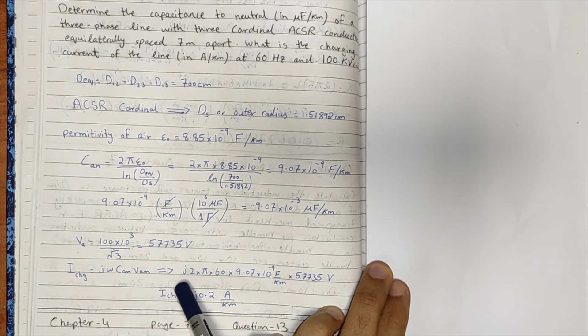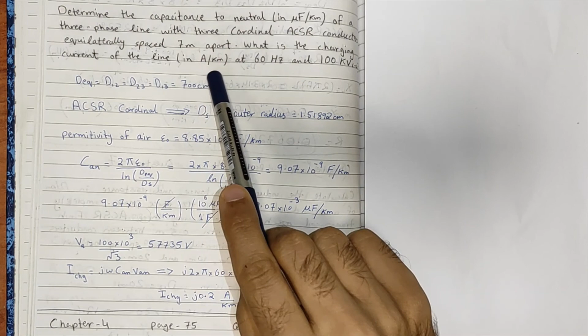Capacitance to neutral is already calculated. But in this formula, we will actually use the farads per kilometer value because of the units. We have to be careful about the units, because the voltage is in volts, which is 57,735, and then farads times voltage will give you amperes per kilometer. Then you just multiply these values, and the charging current will come out to be j 0.2 amperes per kilometer, which was actually asked in the question.